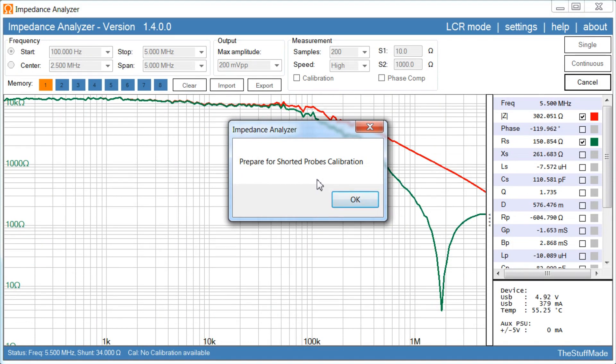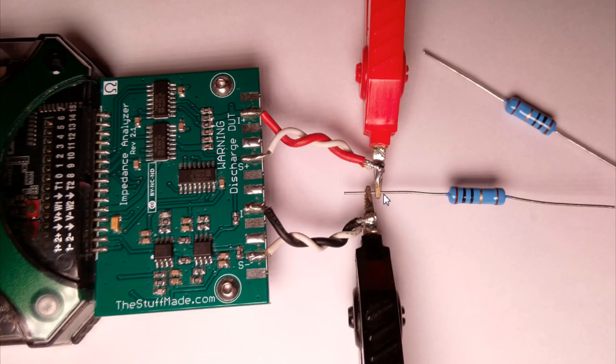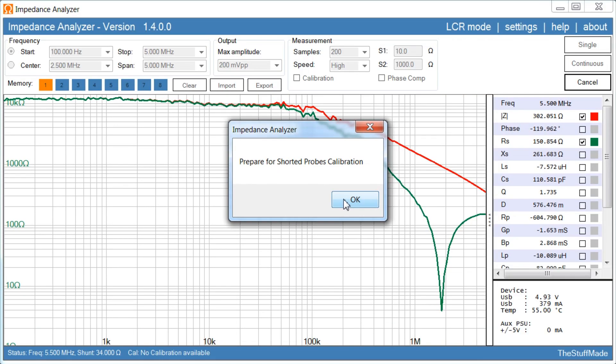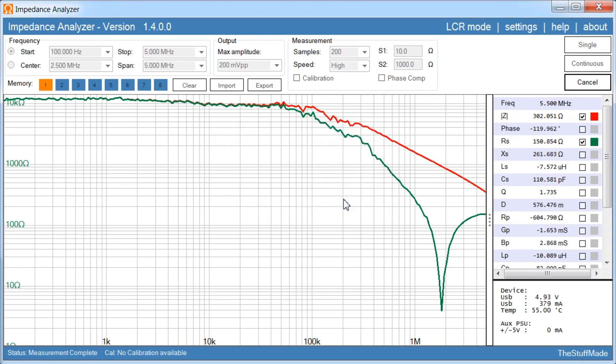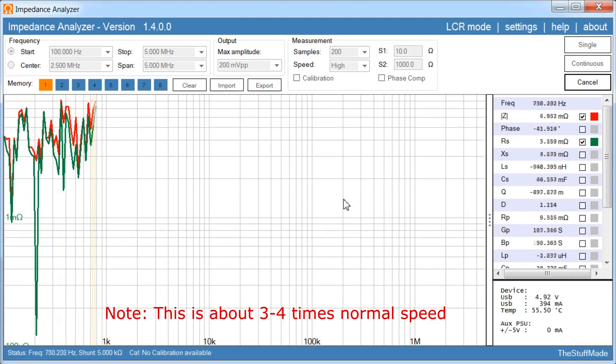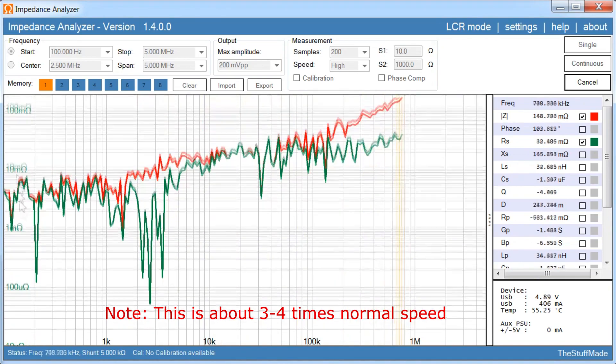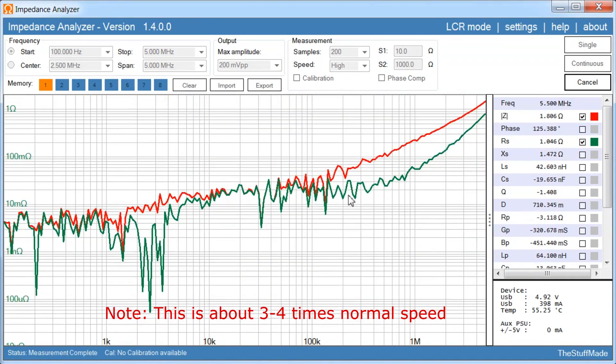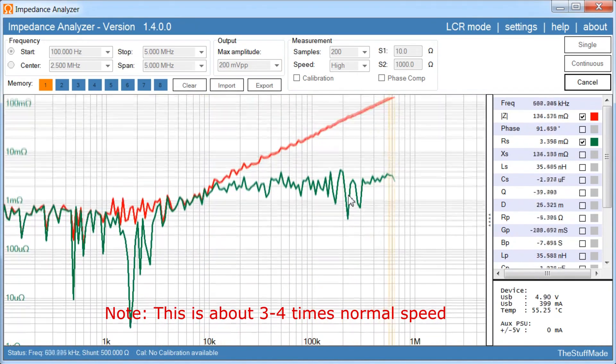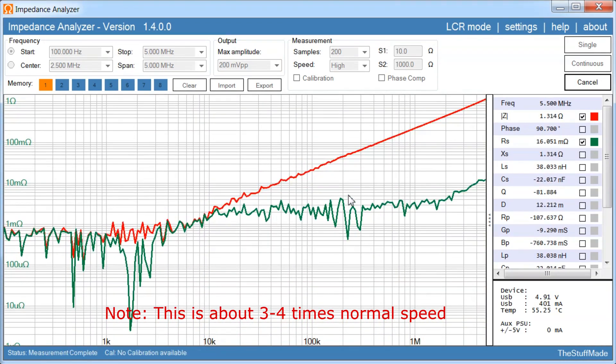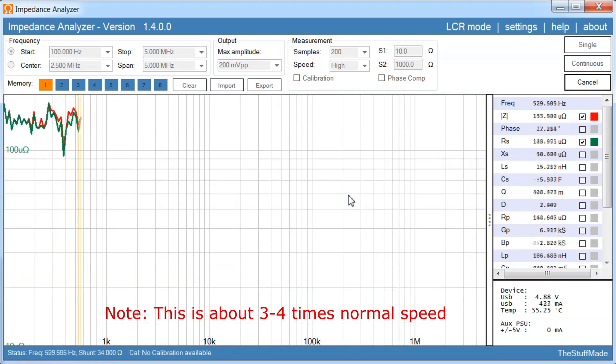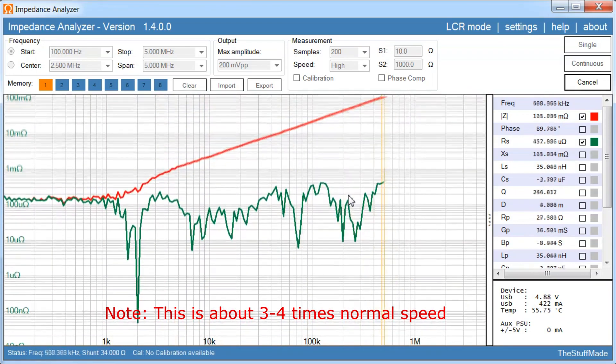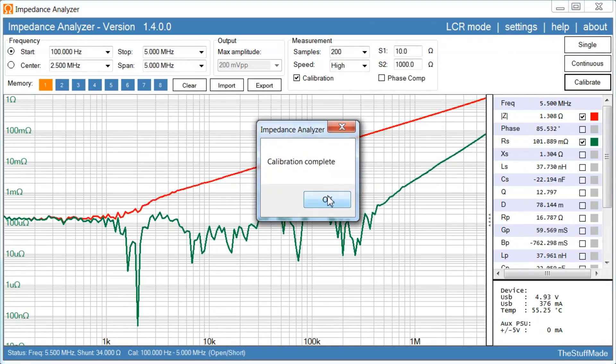Then we prepare for the shorted probes calibration. And again, I like to use a resistor with my Kelvin clips to get a very accurate contact point here. The higher accuracy you have, the better measurements you will get. I will try to demonstrate that later. And click OK. And now you should expect to get very low ohm values, see we are down in milliohms here now. And that's it, the calibration is complete.